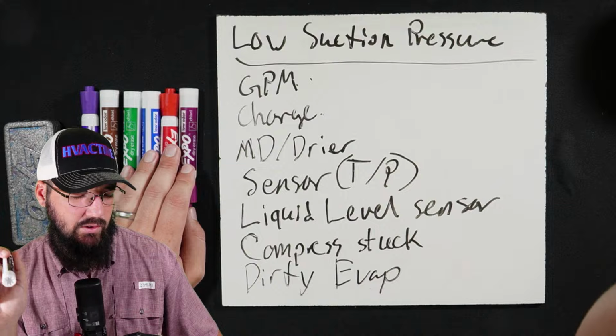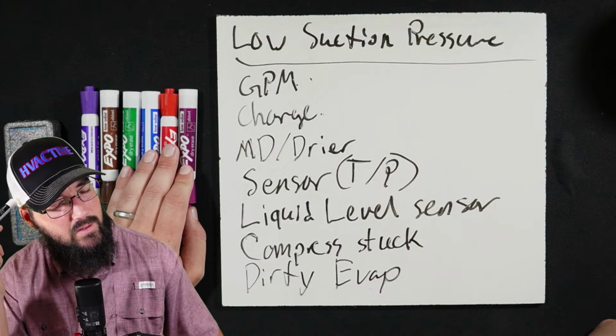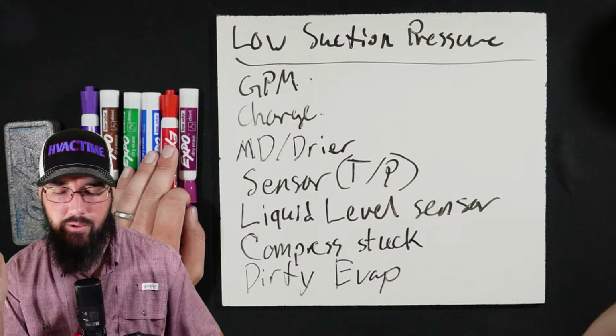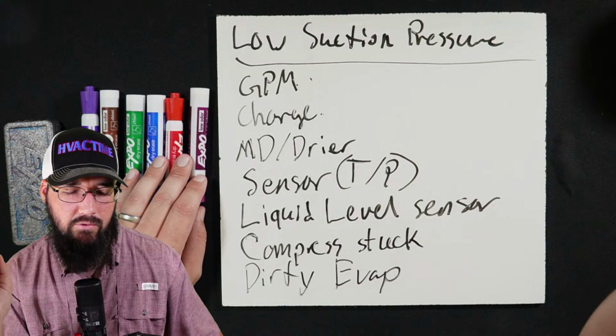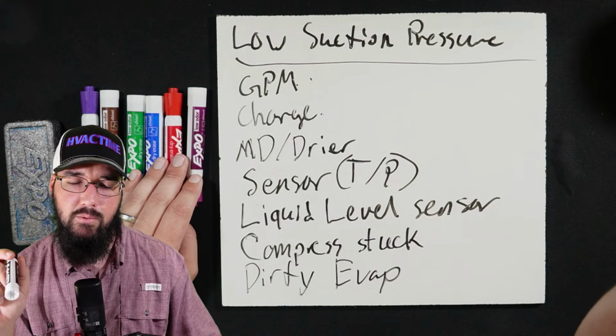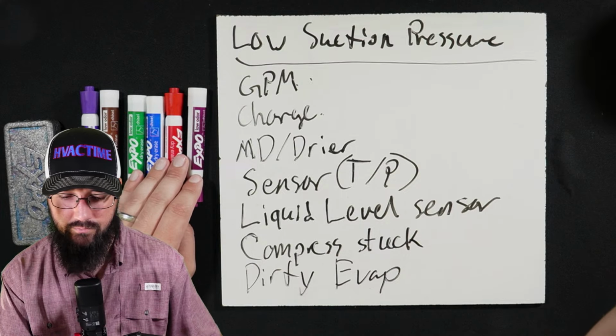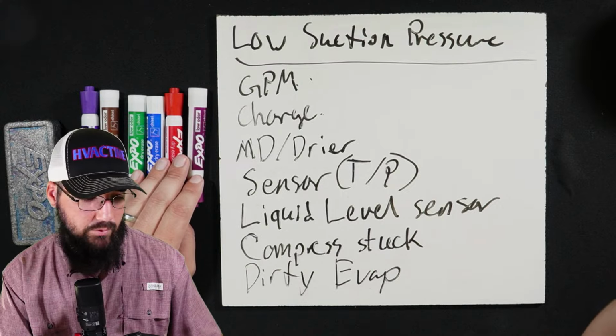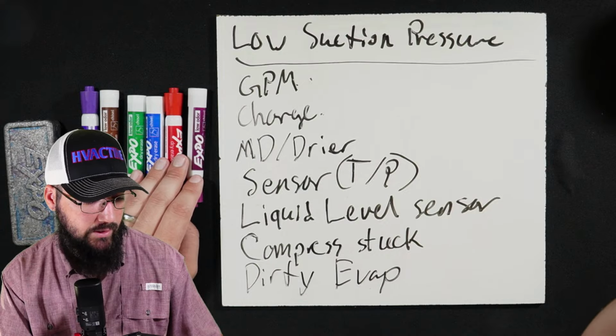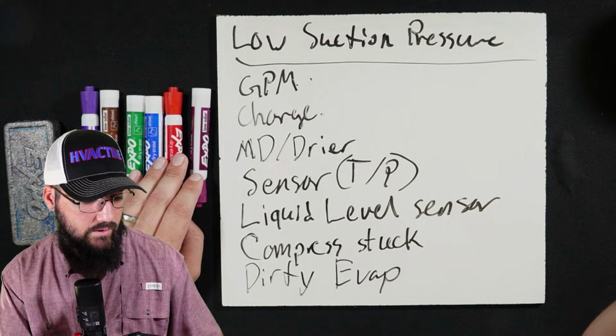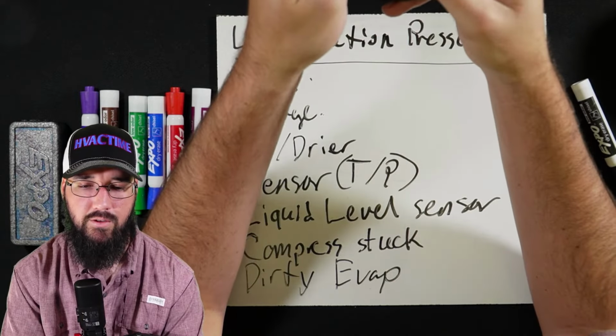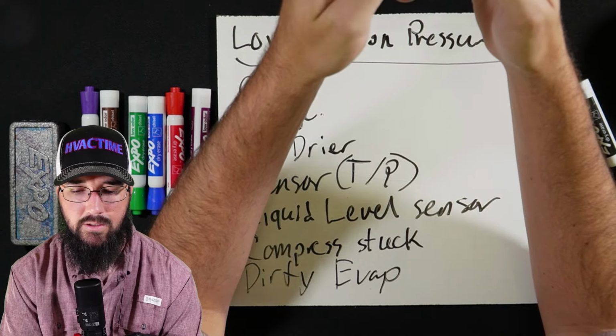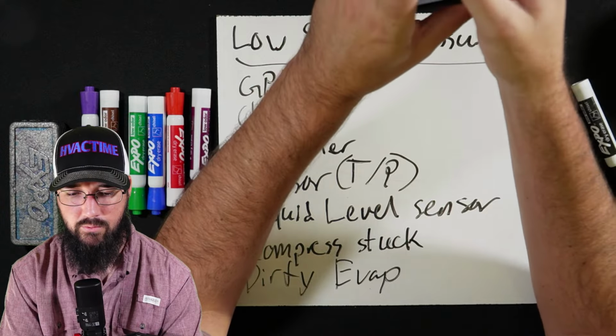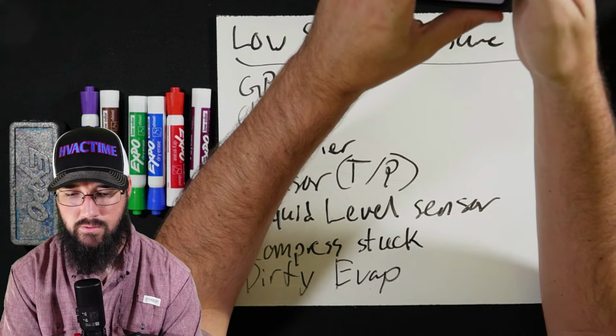Those machines, they have an oil separator, so we shouldn't be stacking oil in the evaporator. I think those also have an eductor, if memory serves. I'd have to pull the manual. I'm trying to think. Why don't we do that real quick? Do these machines have an eductor? Let's go look. Let's pull the manual.